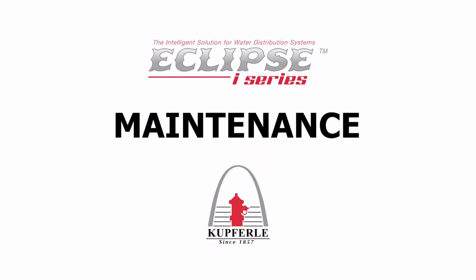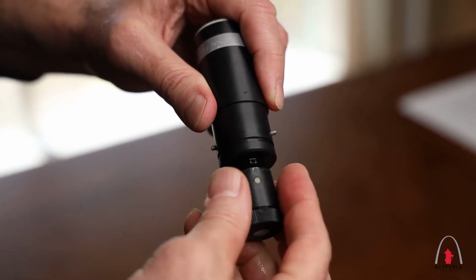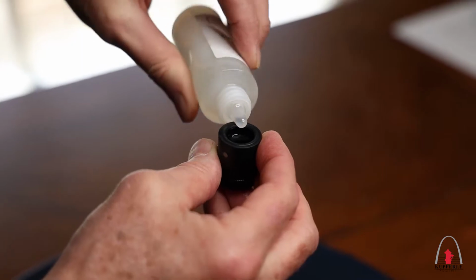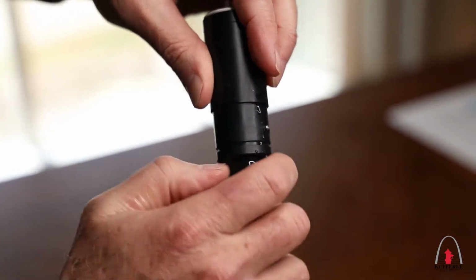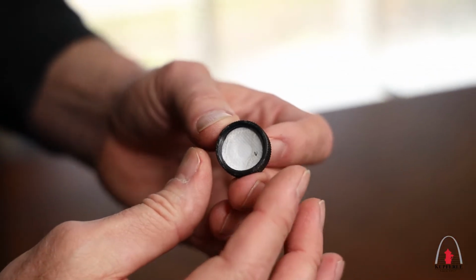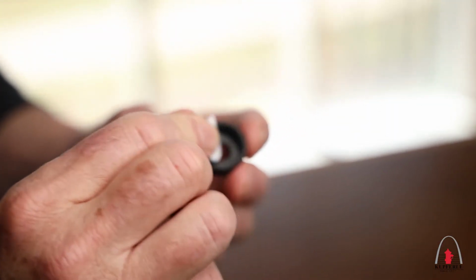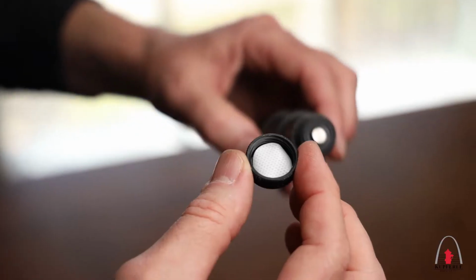To do maintenance on the 9700i Eclipse, first unscrew the chamber for the electrolyte. Refill the chamber and screw it back onto the probe. Next, twist off the cap at the end of the probe. Remove the old membrane and replace it with a new one. Thread the cap back onto the probe.